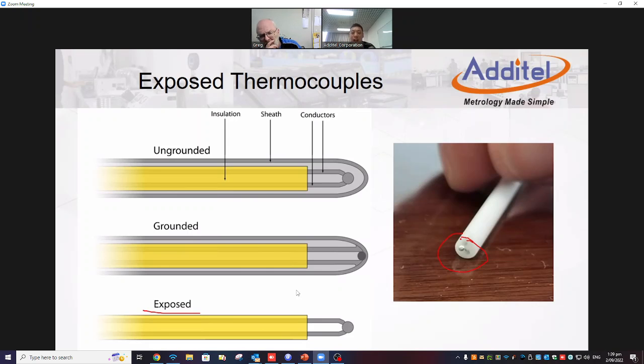You have to cut the line and redo the welding, something like that. That would be a pretty huge problem, a lot of work. So for the exposed thermocouple, no matter if it is a noble metal or base metal, you had better have a sheath outside. This sheath can be ceramic, or what we have is alumina. Those are non-metal materials, so we don't need to worry about contamination.